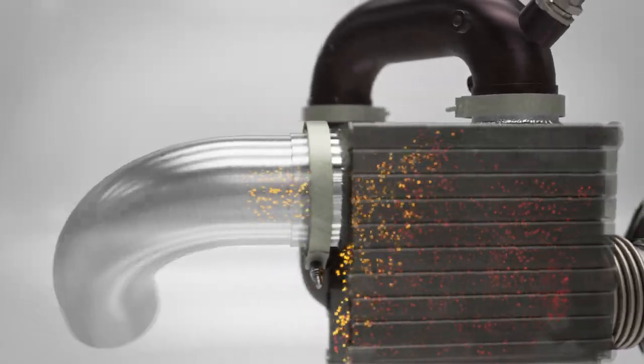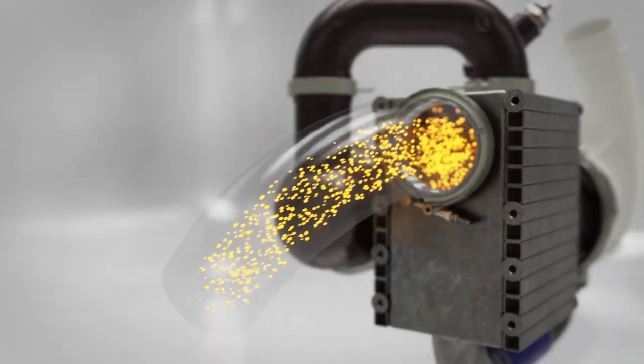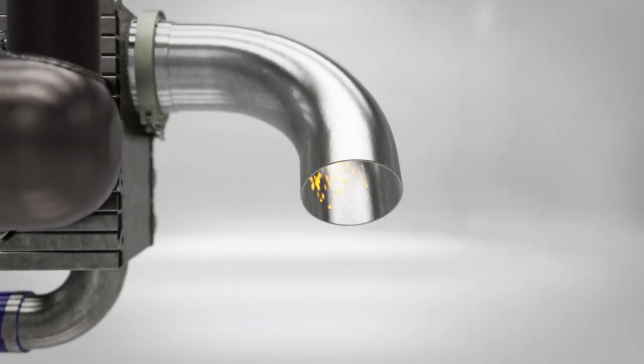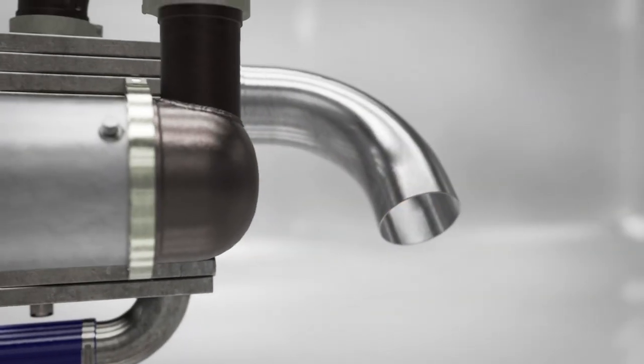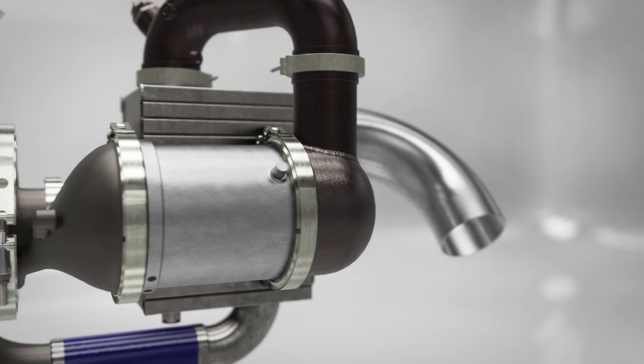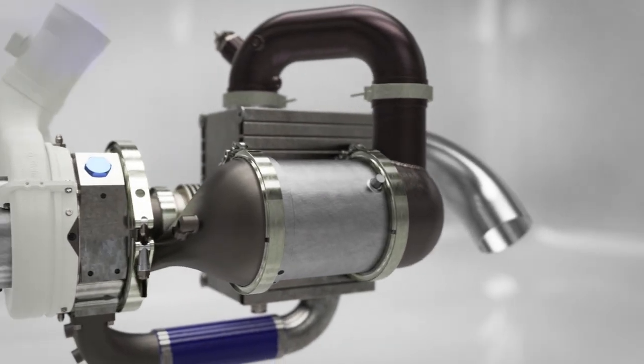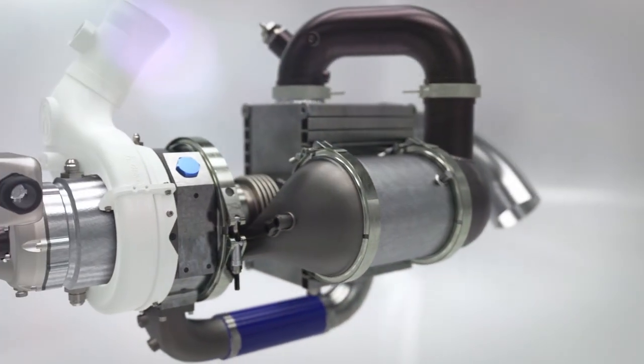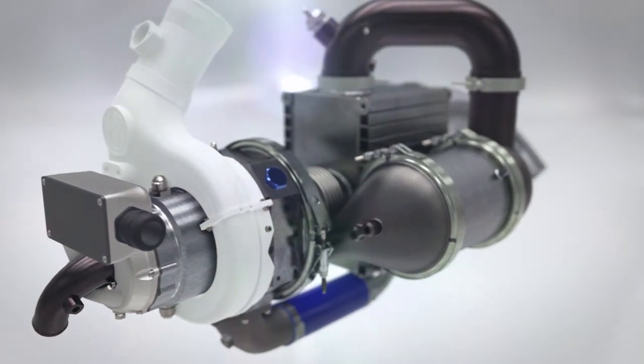The final gases exit the CATGEN at less than 350 degrees Celsius. Thanks to the energy recovered using the heat exchanger, fuel is only used for half of the work, to increase the temperature from 650 to 1050 degrees Celsius. The result of this is increased efficiency and reduced fuel usage.